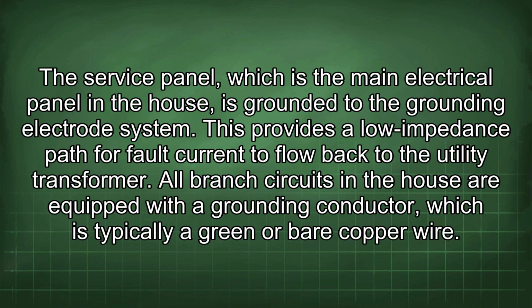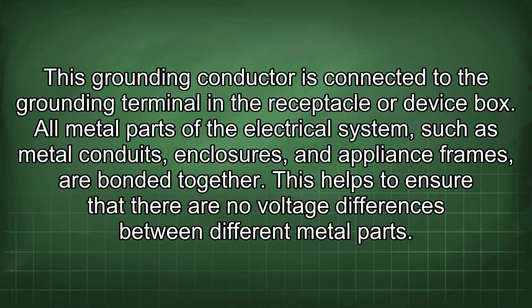The service panel, which is the main electrical panel in the house, is grounded to the grounding electrode system. This provides a low impedance path for fault current to flow back to the utility transformer. All branch circuits in the house are equipped with a grounding conductor, which is typically a green or bare copper wire. This grounding conductor is connected to the grounding terminal in the receptacle or device box. All metal parts of the electrical system, such as metal conduits, enclosures, and appliance frames, are bonded together. This helps to ensure that there are no voltage differences between different metal parts.